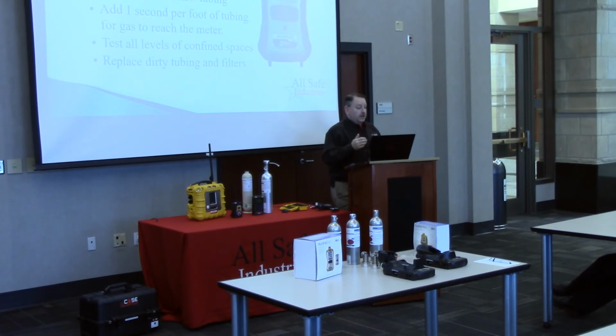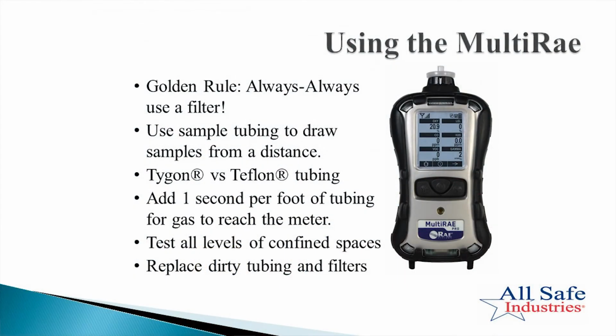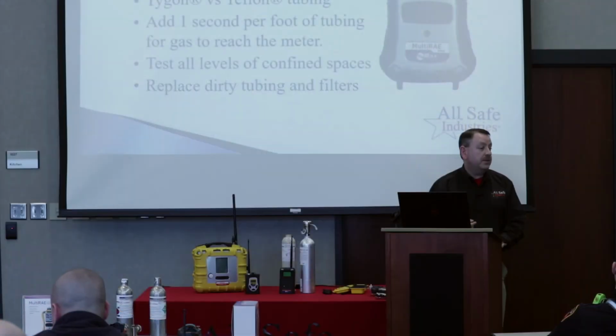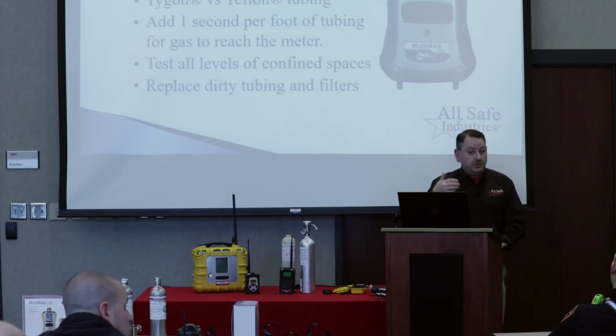So a few things about using your gas meter, especially your MultiRAE. The golden rule is always have that filter engaged in the top of the instrument. That's going to keep out the dust and the dirt and the liquids. Remember, there's circuit boards inside there. Circuit boards don't like to be wet, so make sure there's always a filter attached. Remember, you can use sample tubing to draw gases from a distance, and the Rae Systems meters can use 100 feet of tubing. So if you needed to add 100 feet of tubing, you can do that.